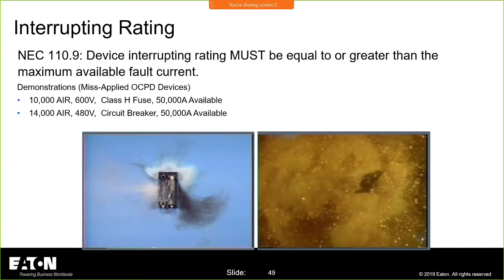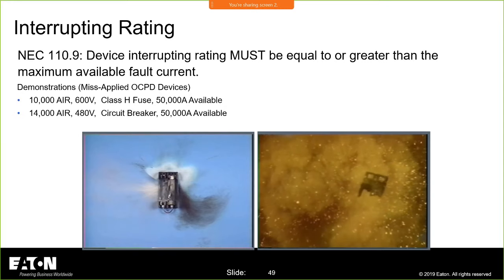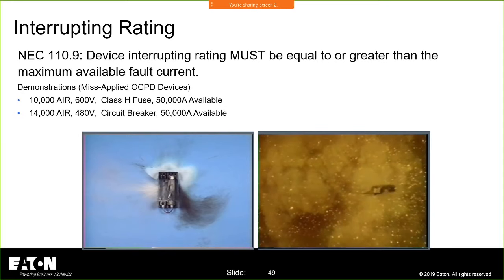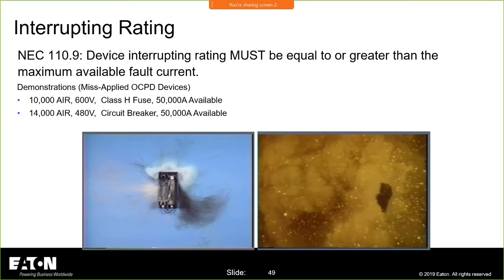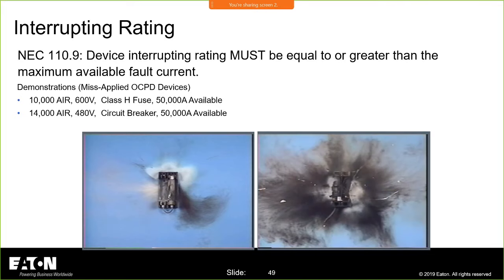And it is indeed a serious misapplication in both of these cases, because we hit a 10,000 amp interrupting rating fuse and a 14,000 amp interrupting rating breaker with 50,000 amps. They're not rated to stop the flow of 50,000 amps. Proper application is very important.